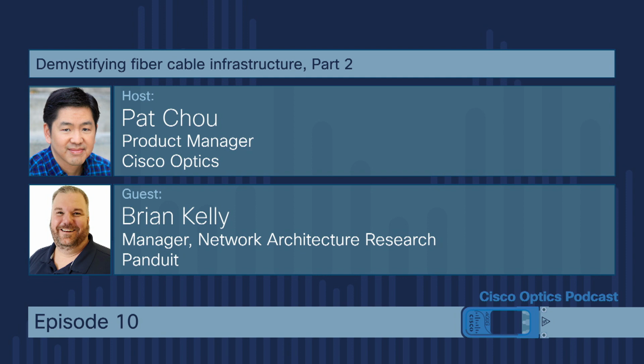It is, if you're going a greater distance than outside of the cabinet, for instance. If you're trying to use any type of structured cabling, you pretty much have to go with the transceiver and fiber option. The reasoning is that the transceiver head on those cables, both the AOCs and the DACs, is really hard to run through any type of pathway and down into another cabinet. It's easy to do one, but if you're doing 30, it becomes really difficult. You probably want to stay away from it if you're running a long distance with a lot of cables.